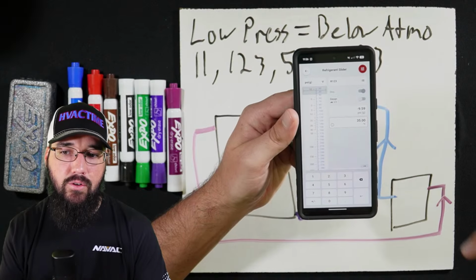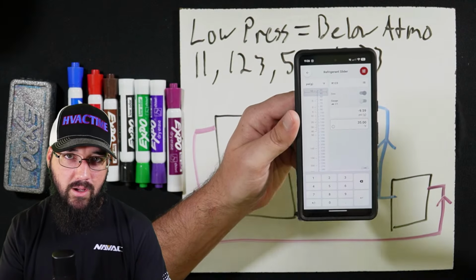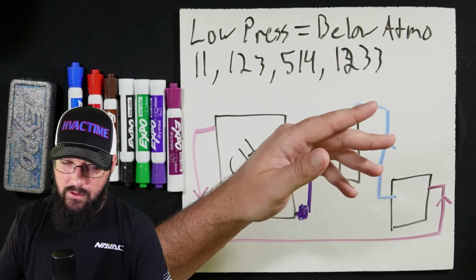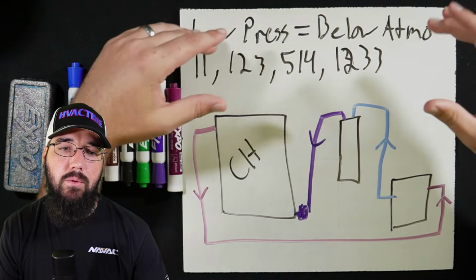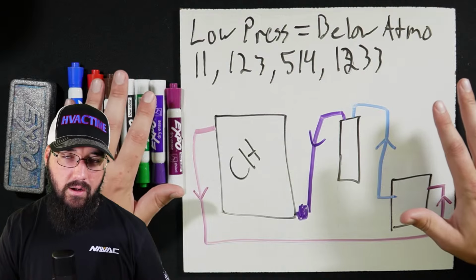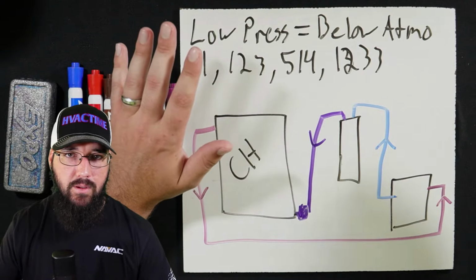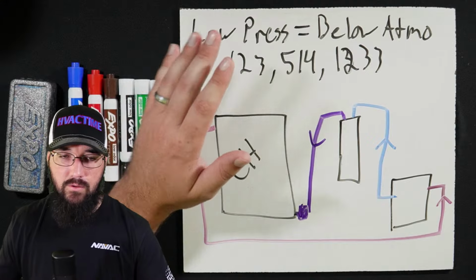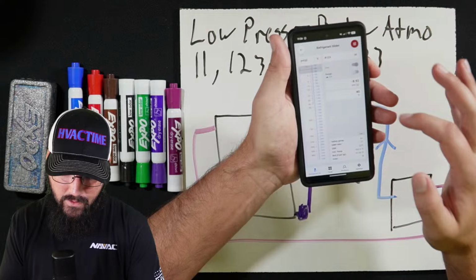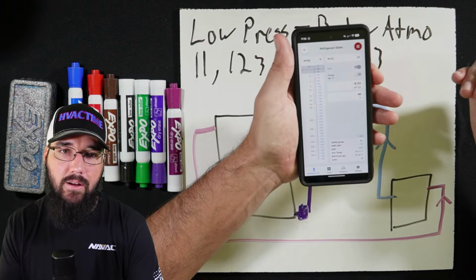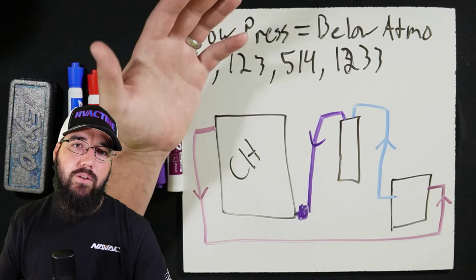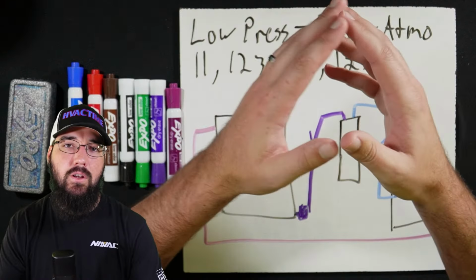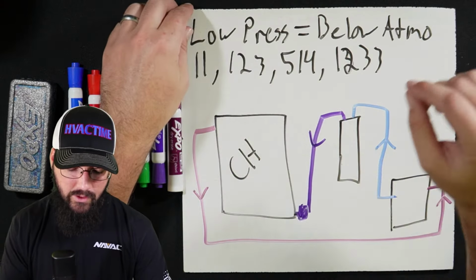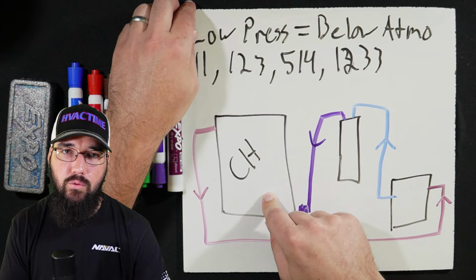Negative 10 psig. Once I've got the cylinder to that pressure with our vapor first, then my concerns about freezing the water go way down. And you could even take it to 40 degrees of saturation, which, okay, what does that mean? So 40 degrees would be basically negative 9 psig.